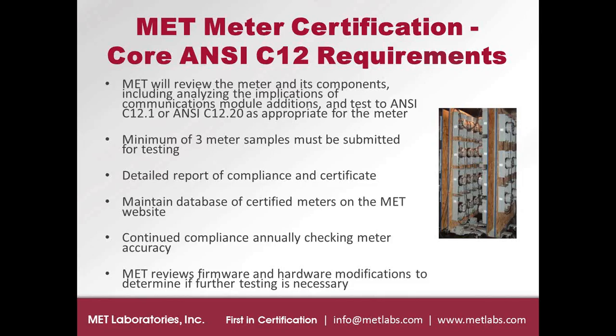Again, 3 samples at a minimum need to be submitted for testing for each test. Most of the time we'll ask for more samples than that. We may ask for 12 samples, 15 samples or more in order to help expedite the test program, where we can break the samples into 3 sample sets, for example, and start a set into the series of tests and run some other concurrent testing on other 3 sample sets.